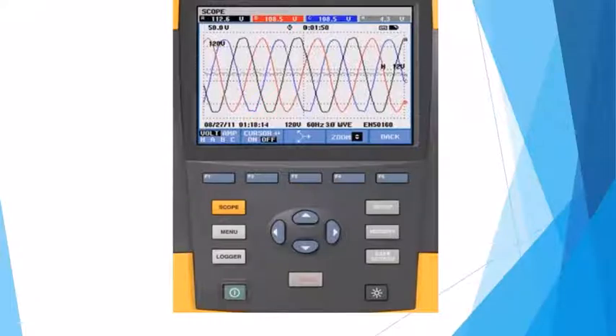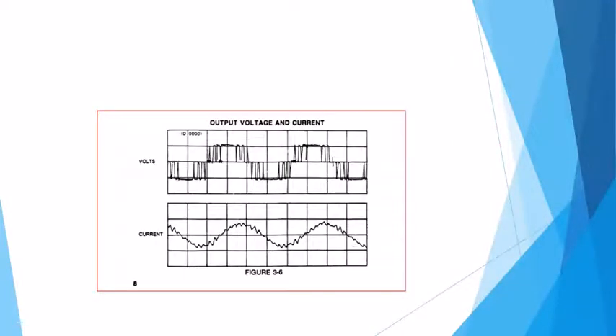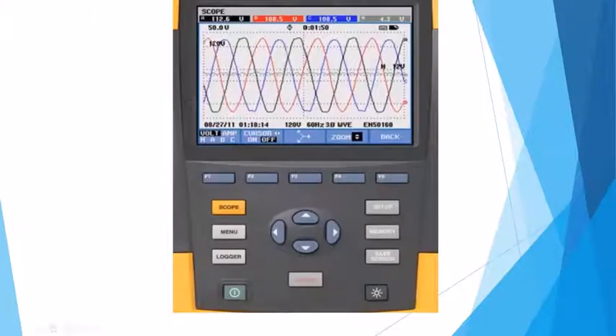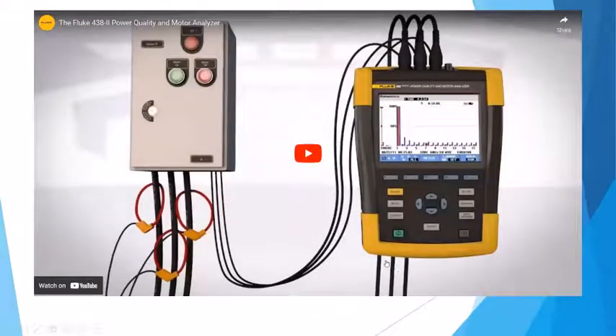So one tool that I use a lot is this Fluke. This happens to be a 434. I think they have a 480-something now. But it's an extremely good tool that allows us to see exactly what's happening, because it actually scopes the waves, the outputs and inputs if you want. You can look at all your voltages line to line, which also helps tremendously. And I'm going to just play a little video. It also has a lot of macros in it that allow you to look at not only the harmonic spectrum they're showing here, but also to set up your flow pressures and information to get additional savings.